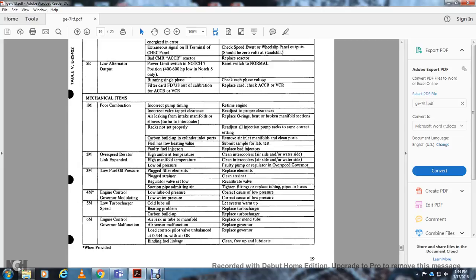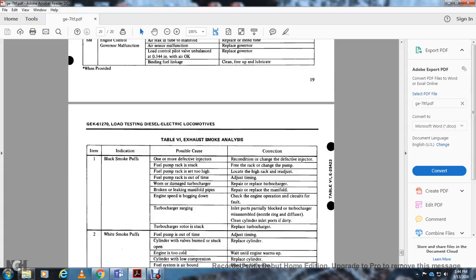All right, item 4M, when provided, engine control governor modulation: low oil pressure, correct cause of low pressure; low water pressure, correct cause of low pressure. Item 5M, low turbocharger speed: cold lube oil, let system warm up. Bearing problem, replace turbocharger. Carbon buildup, replace turbocharger. Item 6M, engine control governor: air leak in the tube of the manifold, replace or mend tube. Air sensor malfunction, replace governor. Load control pilot valve unbalanced at 0.344 of an inch with air okay, replace the governor. Binding fuel linkage, clean and lubricate.